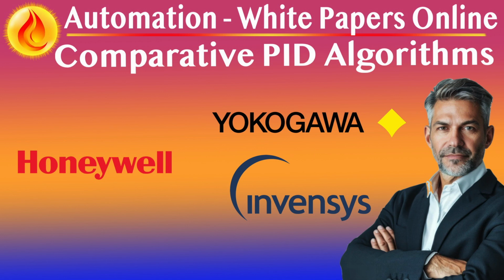Proportional and integral behavior. Yokogawa's ideal implementation provides consistent tuning interpretation across gain changes. In parallel form, engineers can tune P, I, and D independently, but changes in gain affect how I and D behave. Yokogawa also supports explicit integral limits and biasing, enabling fine-grained control in override or constraint-based loops.